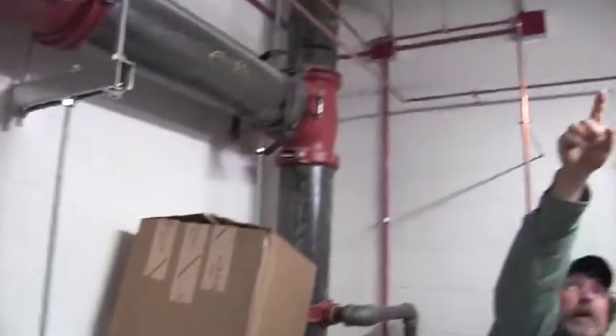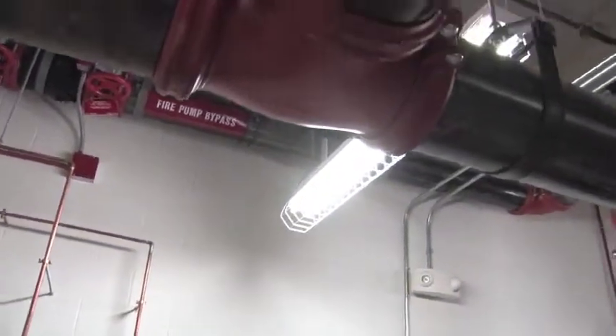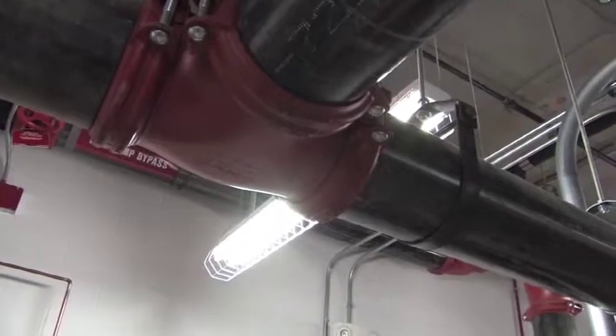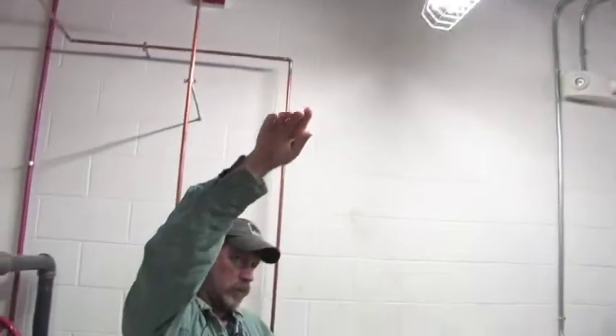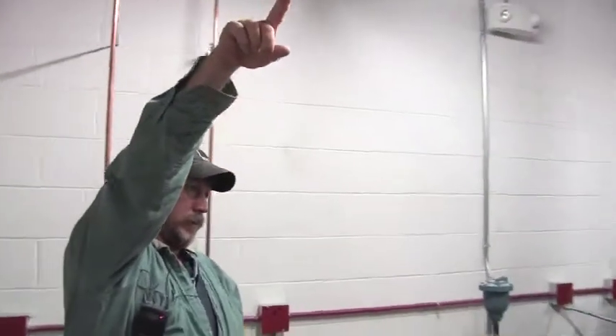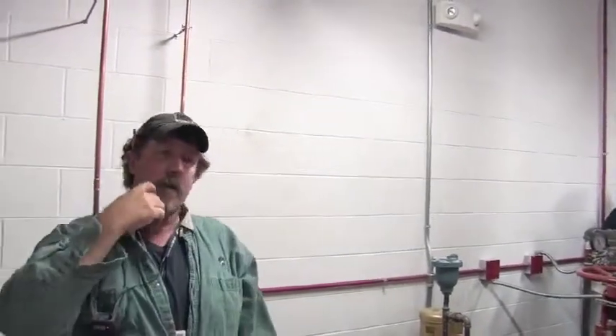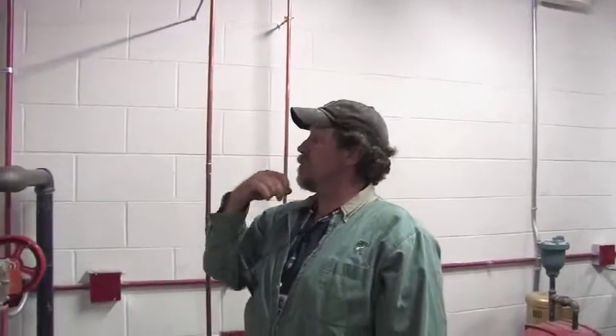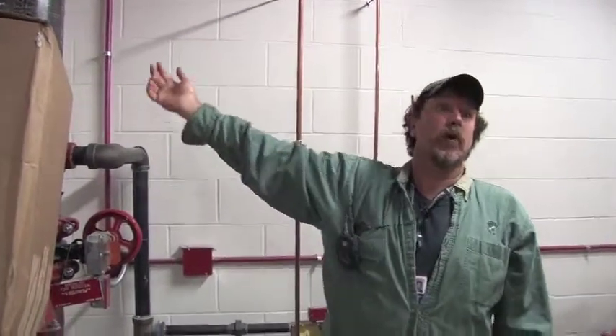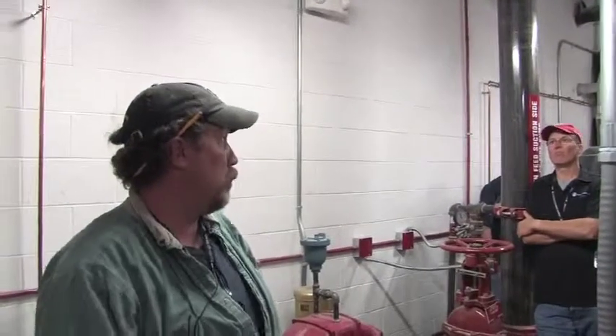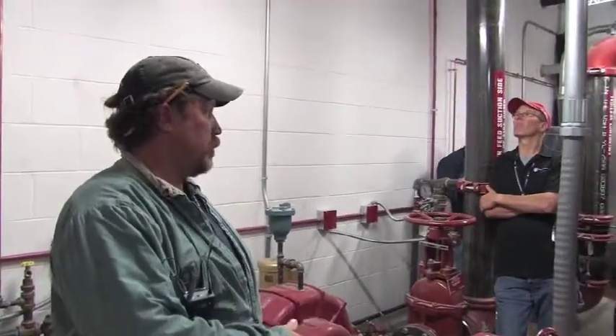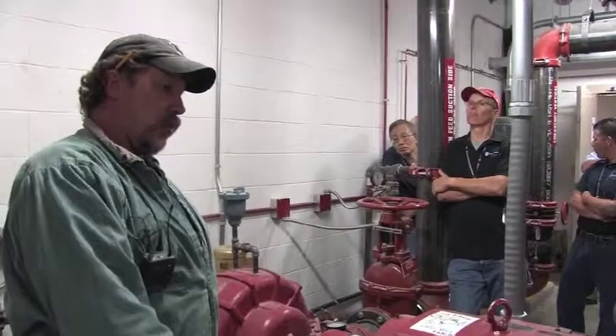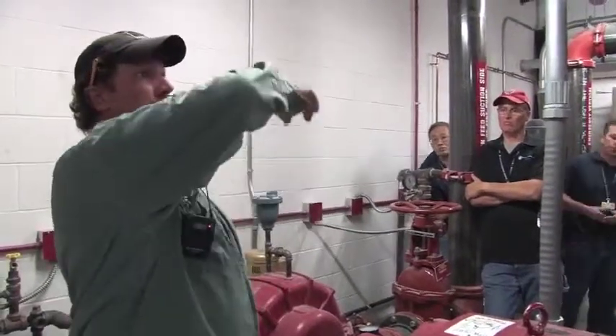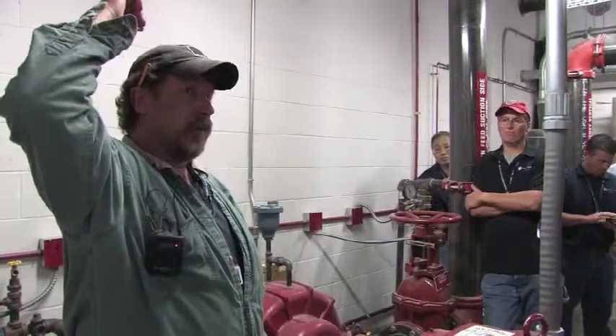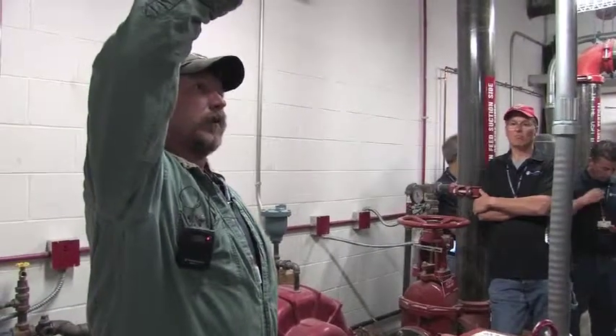This is your test header, which runs all the way down past the elevator lobby, through the fuel tank storage area, and up to the top of the hill over here. And let's see. This pipe comes over here. You also have your vertical turbine over there. If for some reason this pump fails, I believe that'll activate. It's got a holding tank under the floor here. It'll suck water out and help out with putting out the fires and stuff.